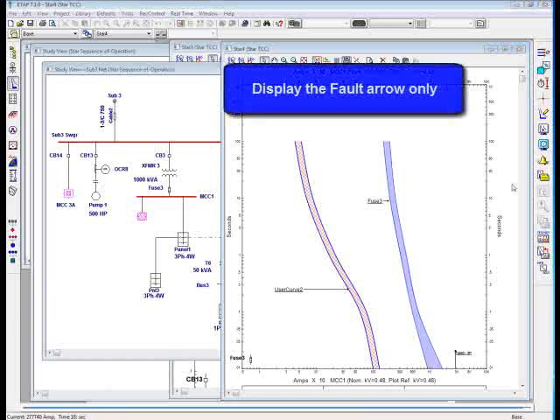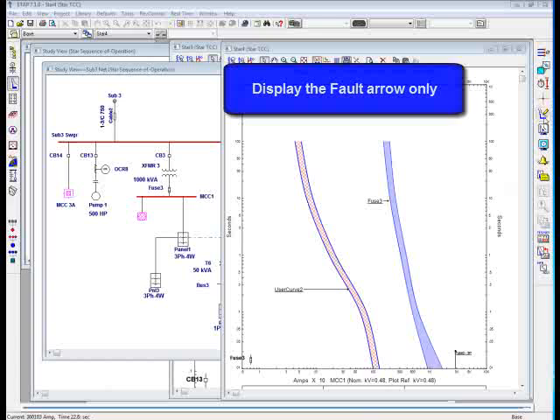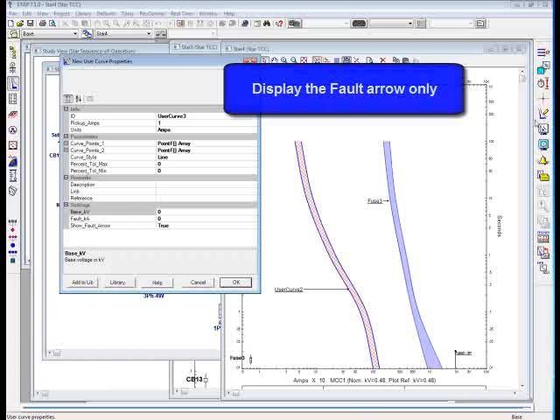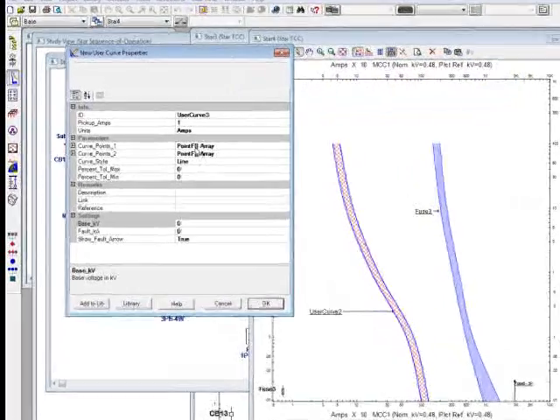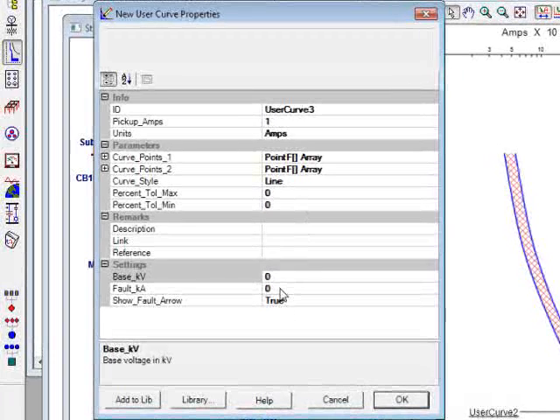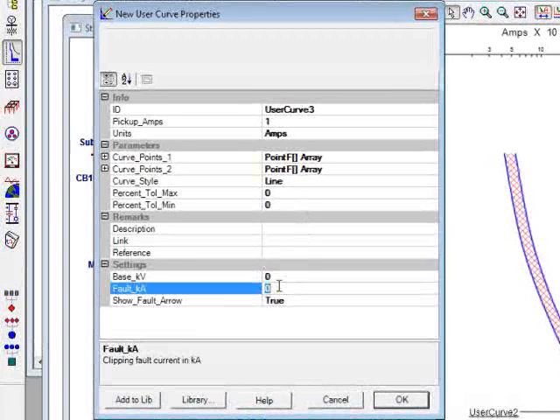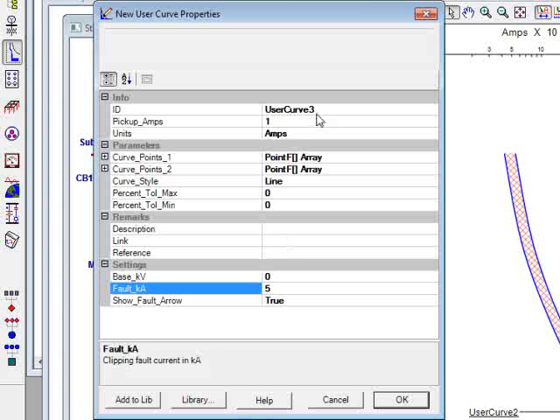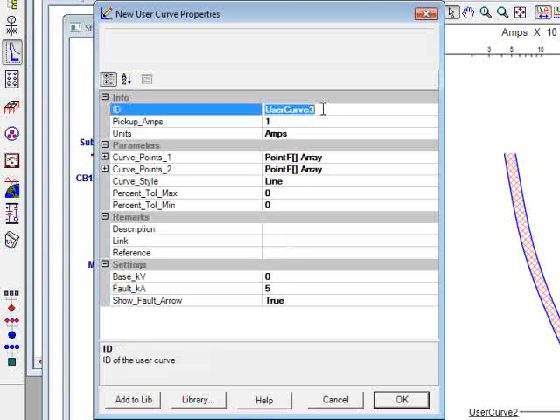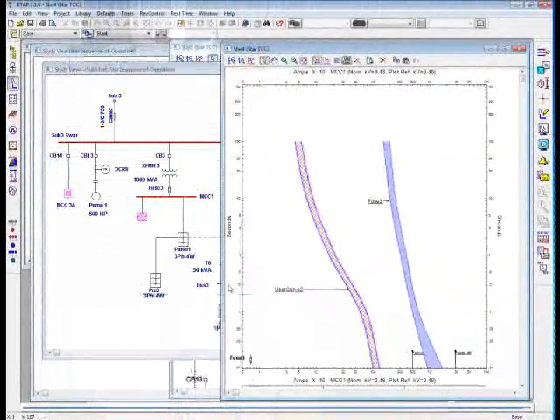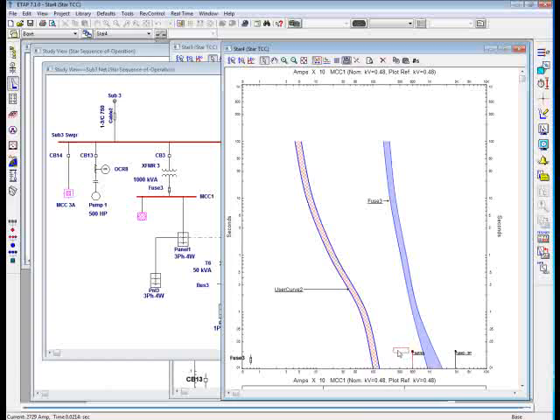Sometimes you wanted to show the fault arrow by itself, and user curve is another good application for showing a fault arrow. So in that case, you don't need to specify any points. All you have to say is just a fault KA. For example, I want to put 5, and I want to just call it as a fault KA as a user curve. As soon as you click OK, this fault arrow shows without connecting to any element.